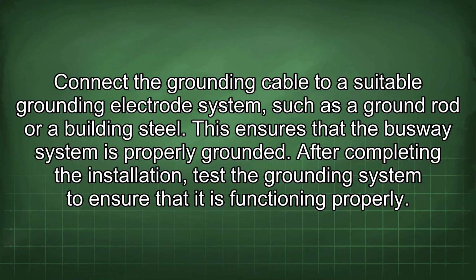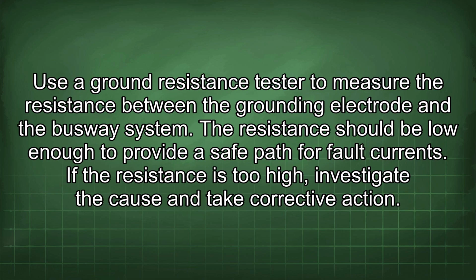After completing the installation, test the grounding system to ensure that it is functioning properly. Use a ground resistance tester to measure the resistance between the grounding electrode and the busway system. The resistance should be low enough to provide a safe path for fault currents. If the resistance is too high, investigate the cause and take corrective action.